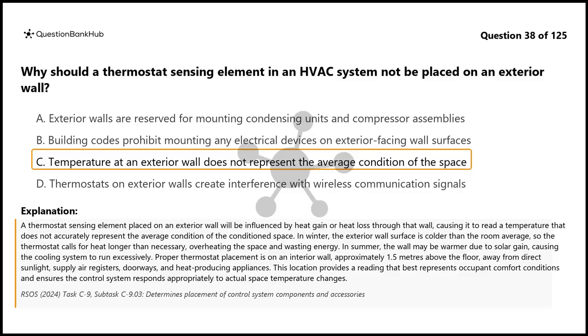Proper thermostat placement is on an interior wall, approximately 1.5 meters above the floor, away from direct sunlight, supply air registers, doorways, and heat-producing appliances. This location provides a reading that best represents occupant comfort conditions and ensures the control system responds appropriately to actual space temperature changes.